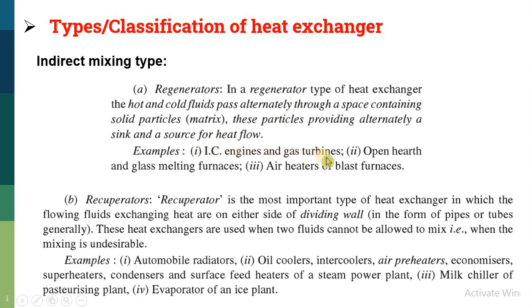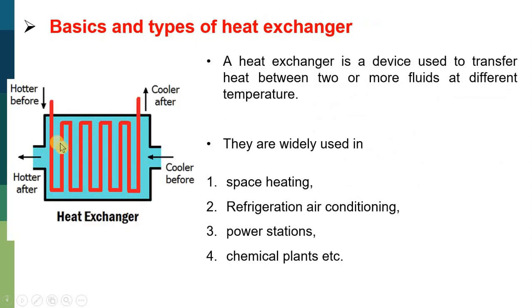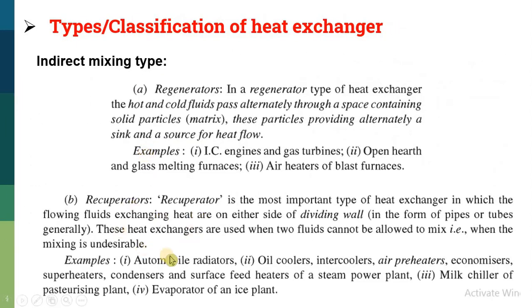Examples of regenerators are IC engines, gas turbines, or air heaters in a blast furnace. Another type is known as a recuperator. A recuperator is the most important type of heat exchanger, in which the fluid flowing through it is divided by a wall in the form of a pipe or tube. The hot fluid passes through the tube and the cold fluid passes over the tube, so both fluids are separated by the tube wall. Examples include automobile radiators, oil coolers, milk chillers, and evaporators in ice plants. All these are examples of the recuperator.